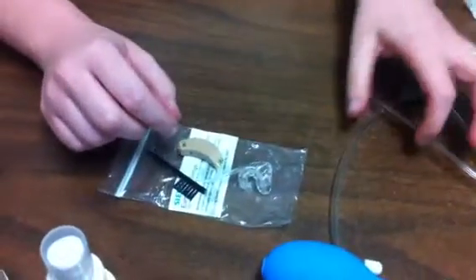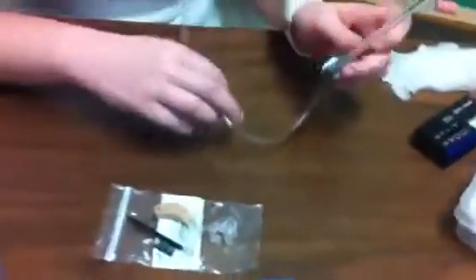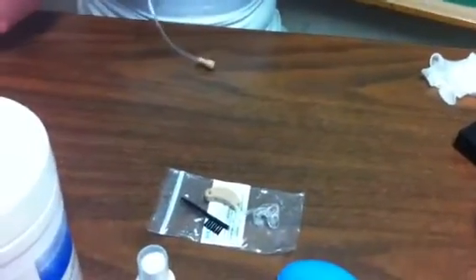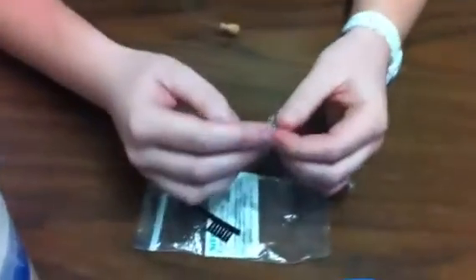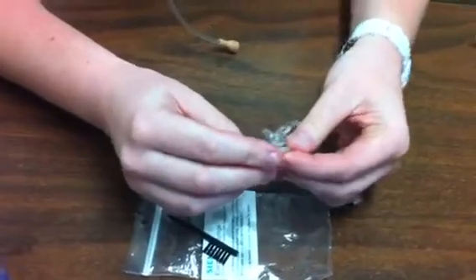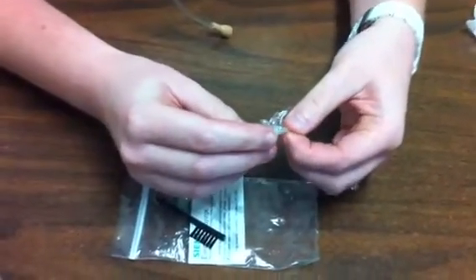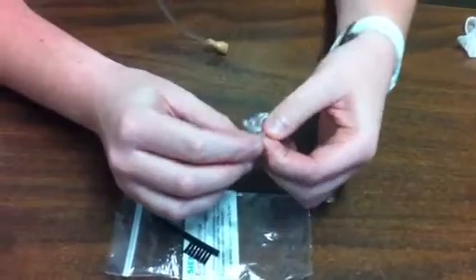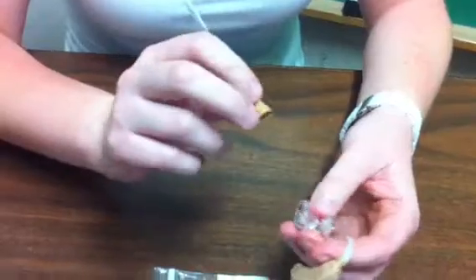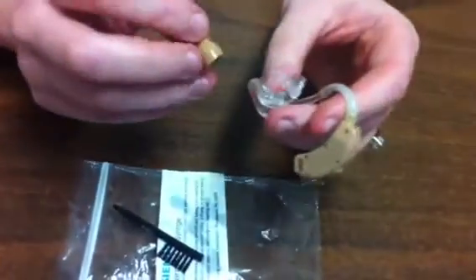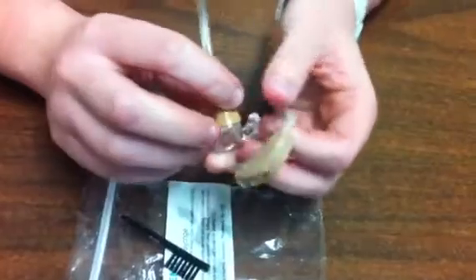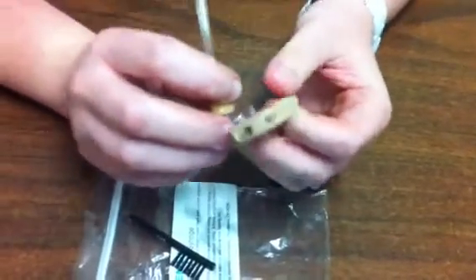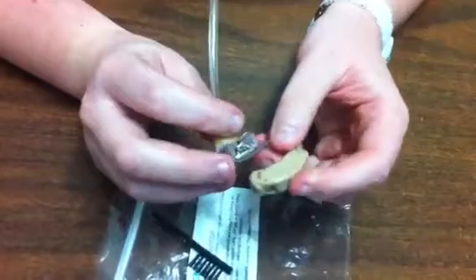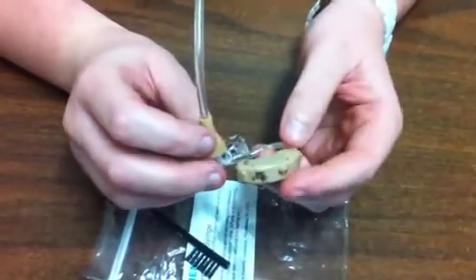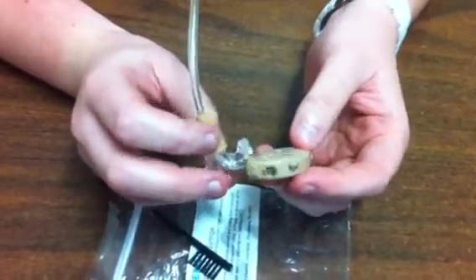Next, you're going to want to check with your ears. You're going to use your stethoscope. Make sure you connect the ear mold to the tube, to the behind the ear portion. Make sure that it's snug. And you're going to want to connect the stethoscope to the ear canal portion of the hearing aid. And you're going to want to do the Ling sound check. It's 6 sounds that cross all frequencies. A, E, U, S, Sh, M.